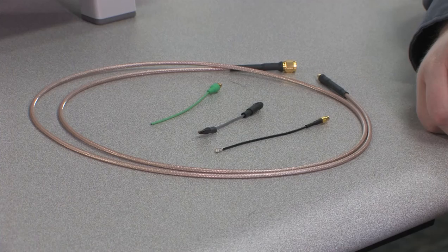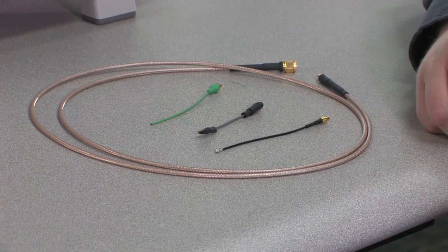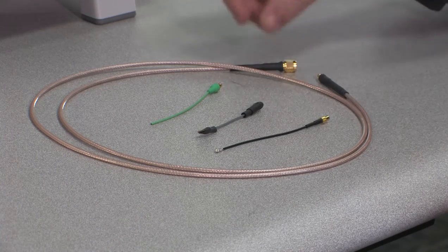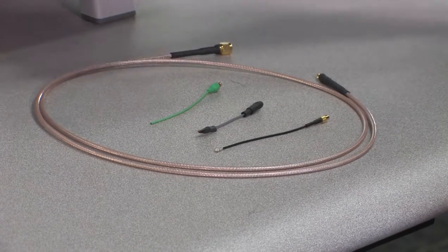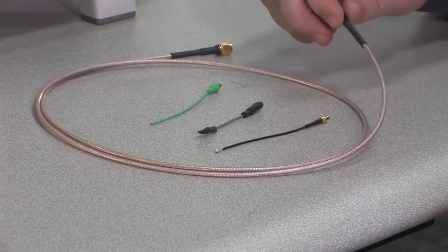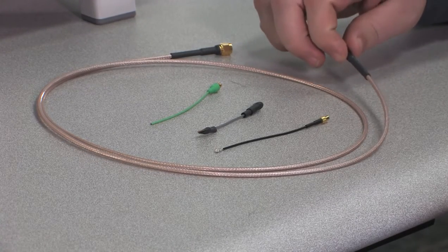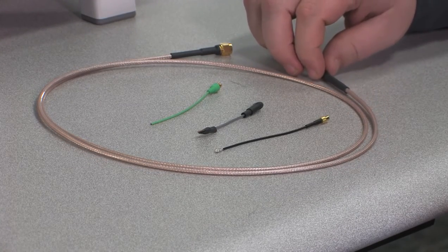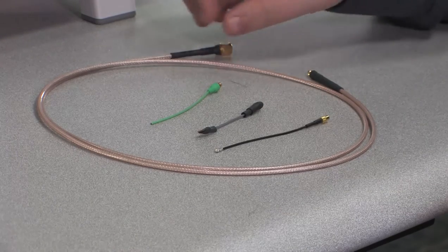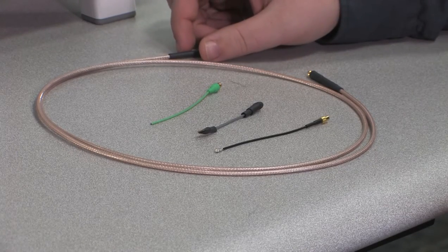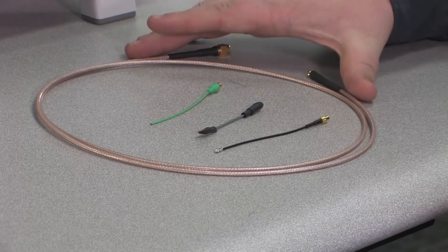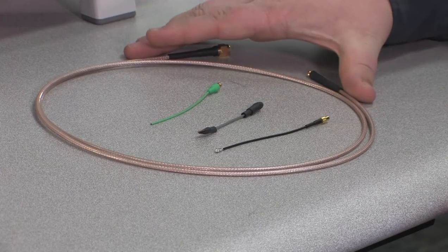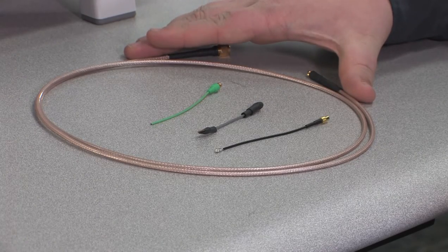We offer a number of accessories for the probe to make connecting to your DUT easier. A cable with an SMA on one end to connect to the probe and an MMCX connector on the other to connect to the accessories is provided. There's also an additional high temp cable that is 2 meters long instead of the standard 1.3 meters for use in test chambers.